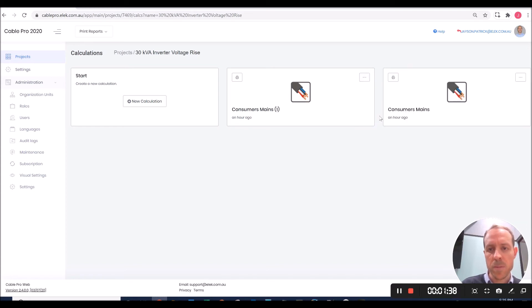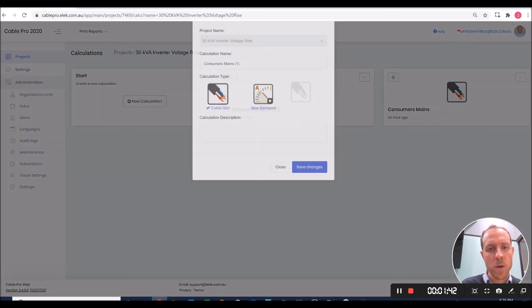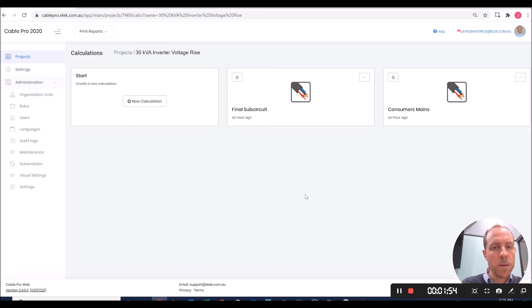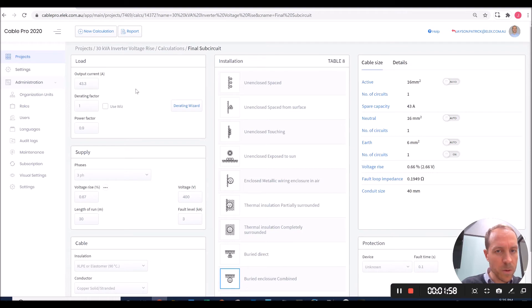I will copy this consumer's mains calculation. I will rename it as final sub-circuit. I'll open this cable calculation. All the inputs should be the same. All we need to do is change the length of run to 60 meters, and the permissible voltage rise to 1.33. Installation is the same. Again, over here we have a minimum cable size of 16 square millimeters and over 60 meters. The actual voltage rise is 1.33%, which meets our requirement.